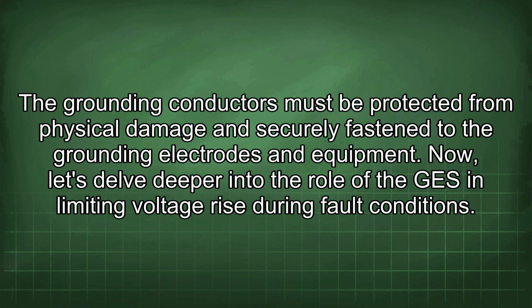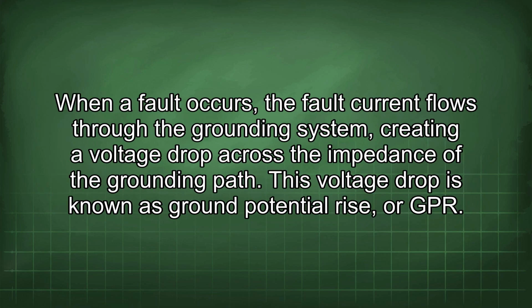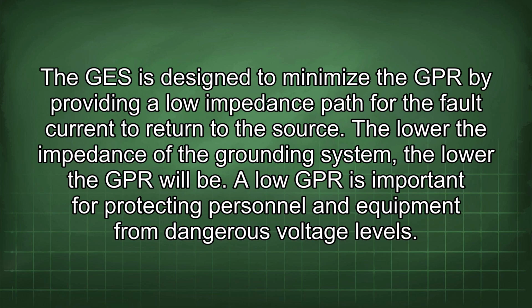Now let's delve deeper into the role of the GES in limiting voltage rise during fault conditions. When a fault occurs, the fault current flows through the grounding system, creating a voltage drop across the impedance of the grounding path. This voltage drop is known as ground potential rise, or GPR. The GES is designed to minimize the GPR by providing a low impedance path for the fault current to return to the source. The lower the impedance of the grounding system, the lower the GPR will be.